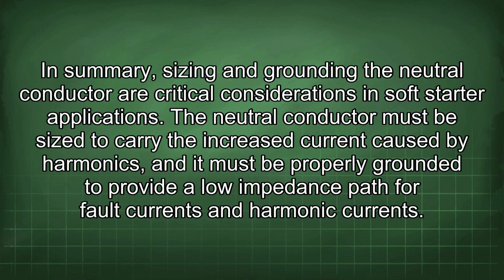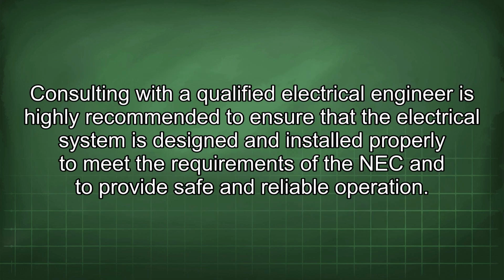In summary, sizing and grounding the neutral conductor are critical considerations in soft starter applications. The neutral conductor must be sized to carry the increased current caused by harmonics, and it must be properly grounded to provide a low impedance path for fault currents and harmonic currents. Consulting with a qualified electrical engineer is highly recommended to ensure that the electrical system is designed and installed properly to meet the requirements of the NEC and to provide safe and reliable operation.